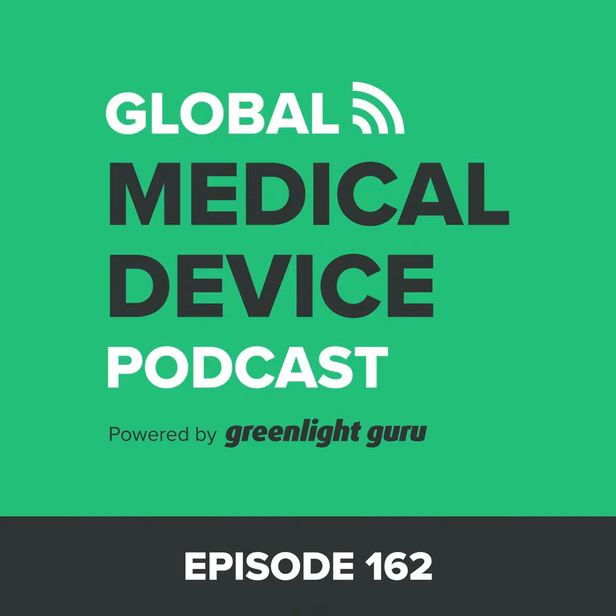Because it's a very uncommonly used pathway to market. It is a pathway that I describe in my Pathways to Market webinar that I did for Greenlight a few months ago. So maybe we can provide a link to that webinar as well. But basically the idea of the PDP, and the PDP, of course, is for class 3 devices, but I'm just using the same regulatory logic to apply to the Special 510(k) here. Basically what we do with the PDP is we agree with the FDA in advance as to how we're going to develop and test the device.